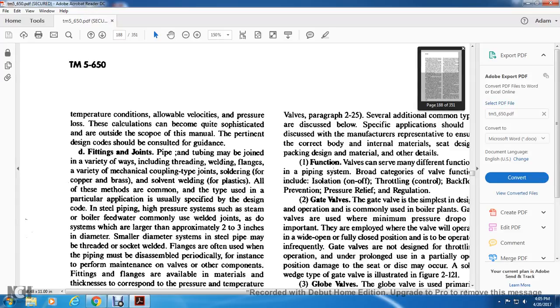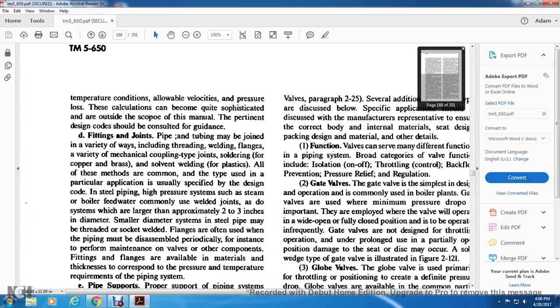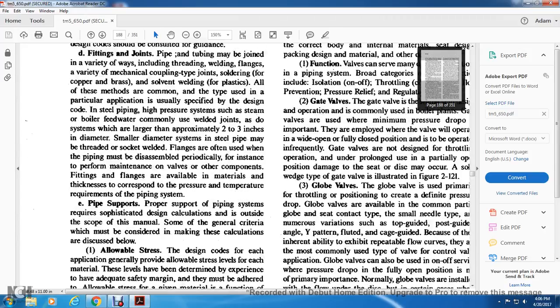The type used for a particular application is specified by the design code. For steel pipe and high pressure systems such as the steam boiler feed water, welded joints are commonly used, as are systems of larger size, approximately 2 to 3 inches. Small diameter steel pipe systems may be threaded or socketed. Welded flanges are often used where the piping may be disassembled periodically, for instance for performance maintenance of valves and other components. Fittings and flanges are available with material thickness corresponding to the pressure and temperature requirements of the piping system.